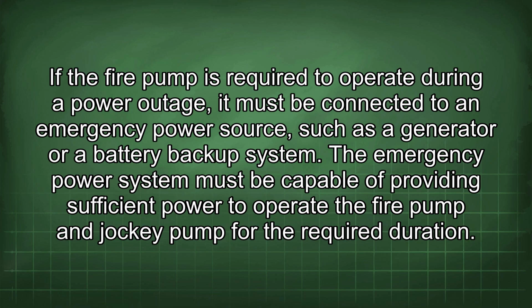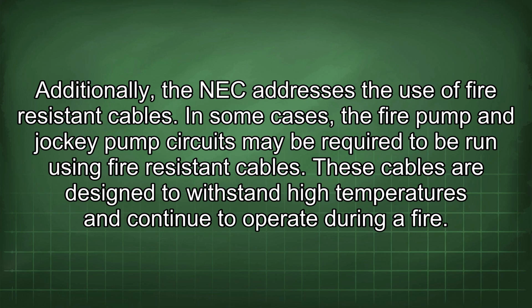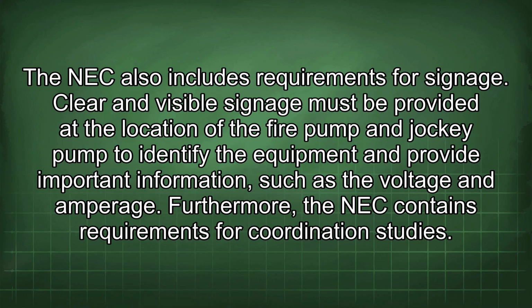The emergency power system must be capable of providing sufficient power to operate the fire pump and jockey pump for the required duration. Additionally, the NEC addresses the use of fire-resistant cables. In some cases, the fire pump and jockey pump circuits may be required to be run using fire-resistant cables. These cables are designed to withstand high temperatures and continue to operate during a fire. The NEC also includes requirements for signage. Clear and visible signage must be provided at the location of the fire pump and jockey pump to identify the equipment and provide important information such as the voltage and amperage.